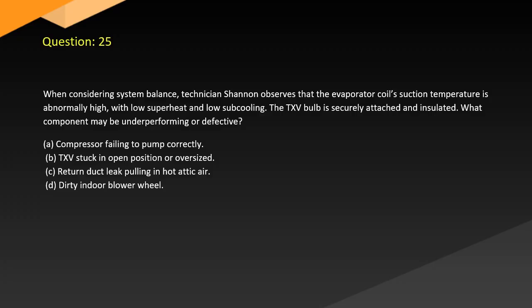Question 25. When considering system balance, technician Shannon observes that the evaporator coil's suction temperature is abnormally high, with low superheat and low subcooling. The TXV bulb is securely attached and insulated. What component may be underperforming or defective? A. Compressor failing to pump correctly. B. TXV stuck in open position or oversized. C. Return duct leak pulling in hot attic air. D. Dirty indoor blower wheel.